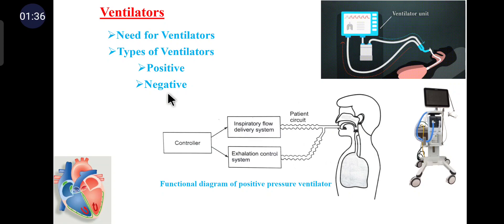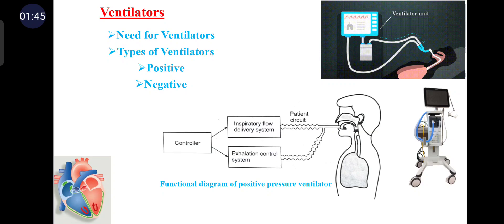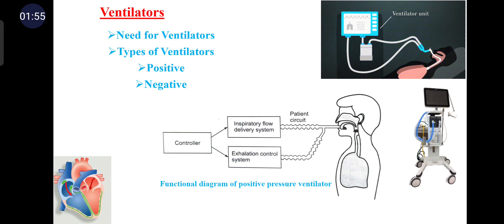The negative pressure moves the thoracic walls outward, expanding the intrathoracic volume and dropping the pressure inside the lungs, resulting in a pressure gradient between the atmosphere and the lungs, which causes the flow of atmospheric air into the lungs. The inspiratory and expiratory phases of respiration are controlled by cycling the pressure inside the body chamber.